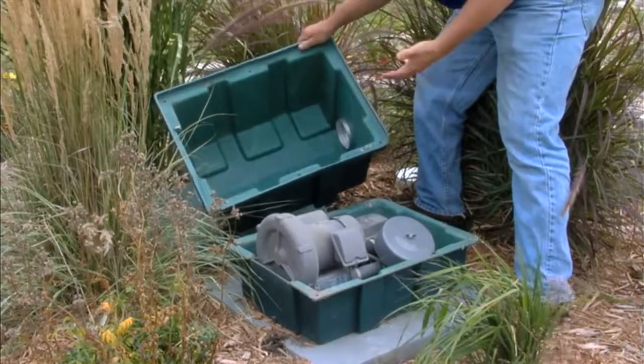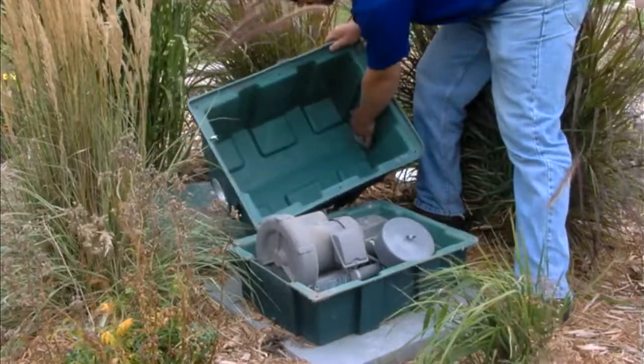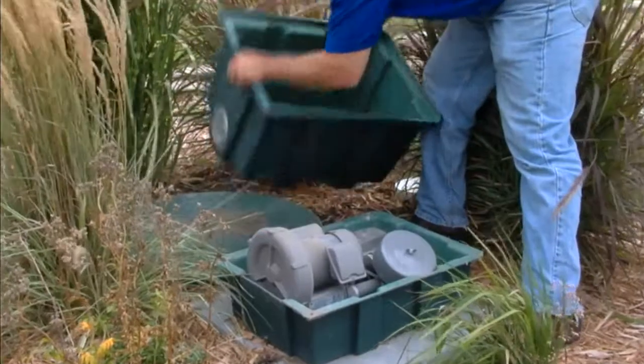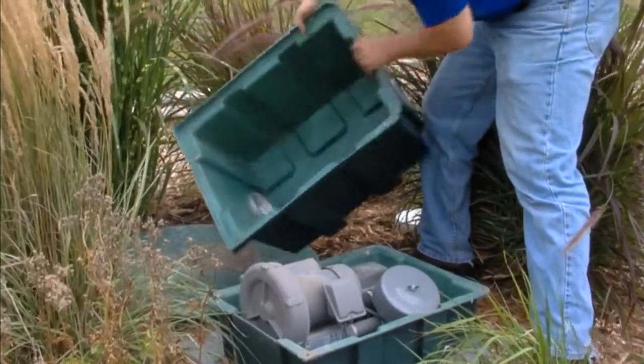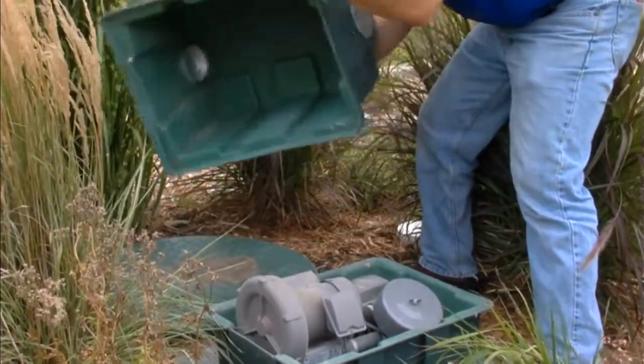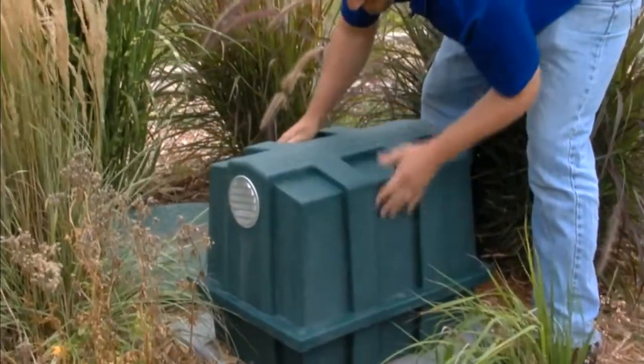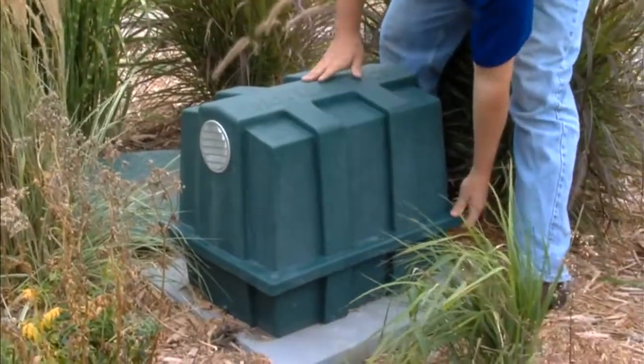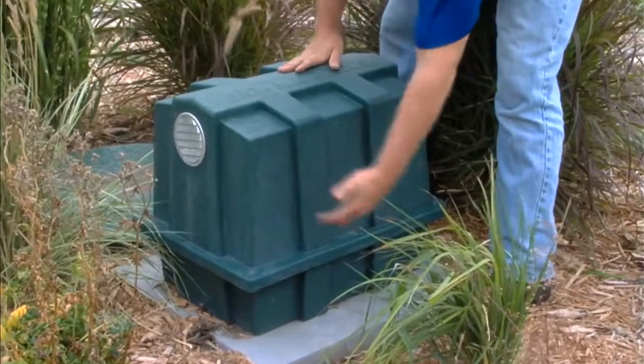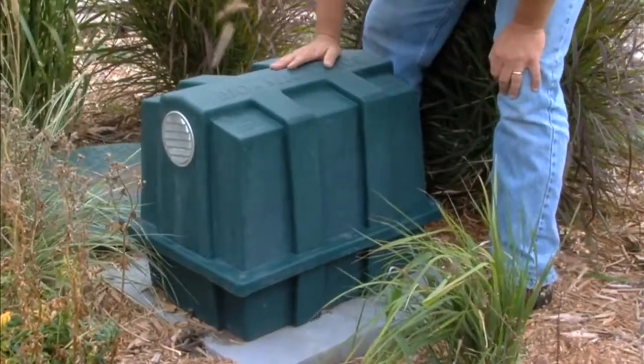Okay, after we're done checking all the physical parts of the blower and connections, we're going to put our blower housing cover back on. But first, we're going to want to check the louvers on each end of the housing, make sure they're clear, make sure they're not obstructing airflow. These look good and clear. So we're going to put our blower housing cover back on. It's a keyed blower housing, so it only fits one way. And then you're going to put your screws back in place, secure the blower housing back in place.